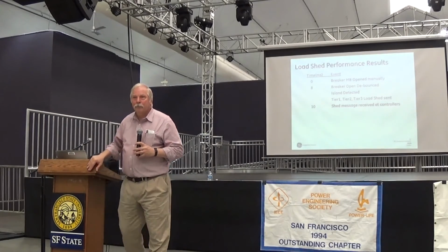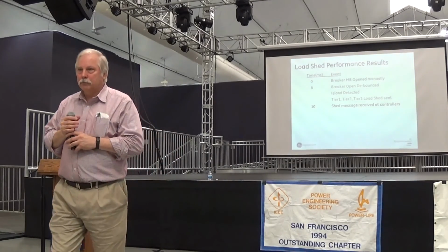So the deceleration is due to the load shedding? Well, not due to the governor response? No, and that's a good question. The deceleration, there was no load shed on acceleration, so I do not shed load on an unbalanced island. The governor response slowed down the generators.